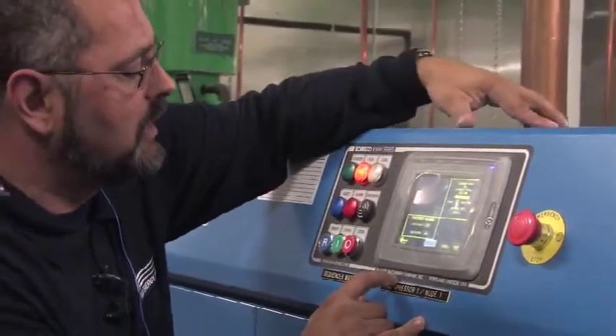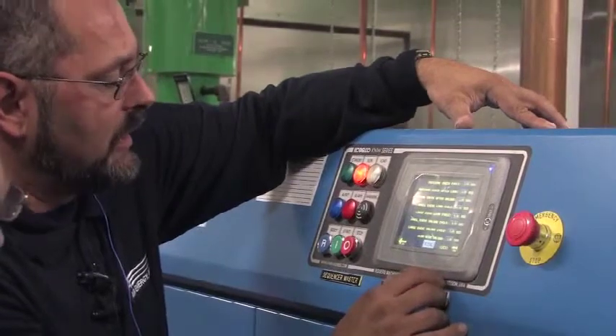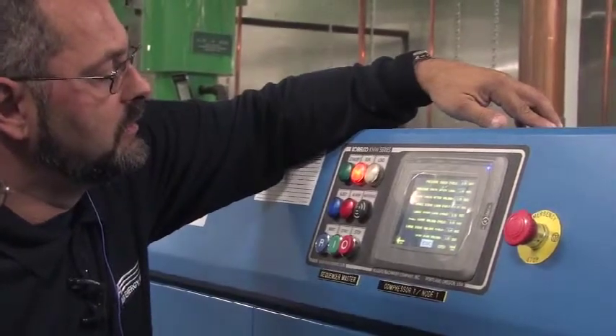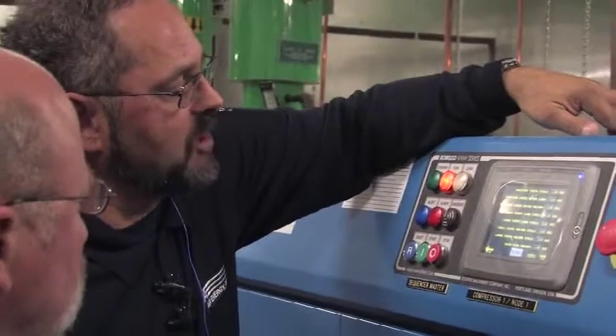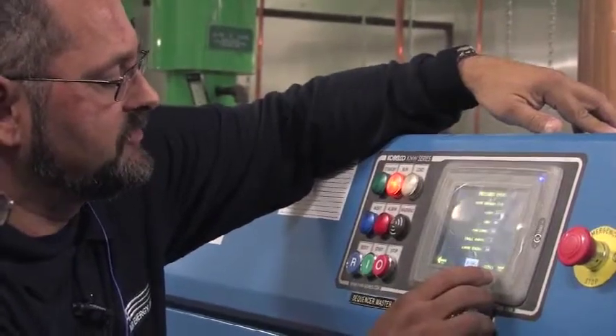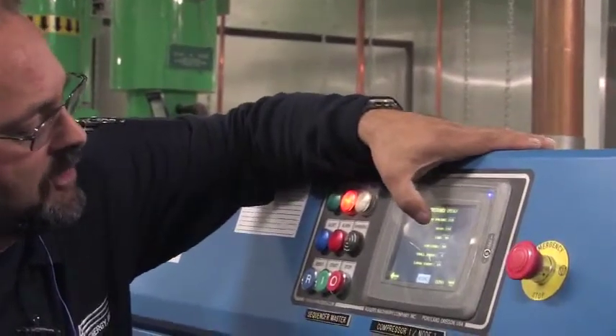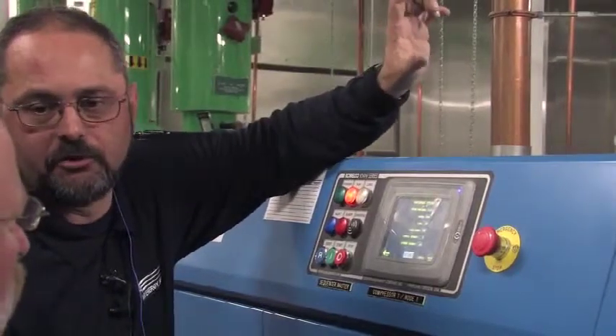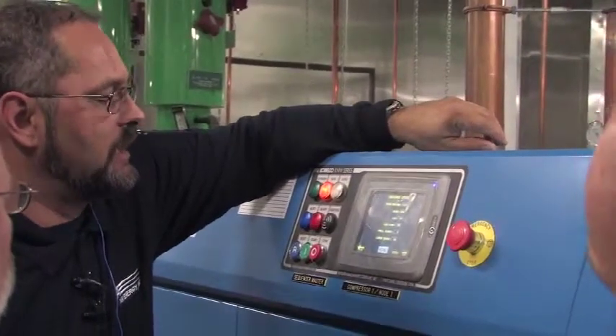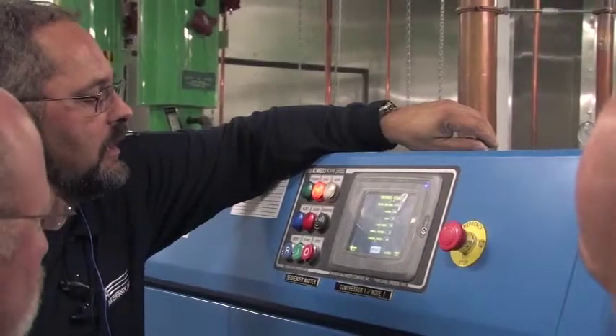Time clock, you know, if you got an alarm, pressure high and low. How often it checks the pressure: basically it scans every 2 seconds. Small event, large event cycles. These are all adjustments. Now this is what I was talking about as far as pressure. High and low is 110. The normal high and low are your settings where you want to keep the system. You know, that's what you're really looking to keep things between. So if it goes high or low, I'm going to get an alarm? Yes. And like I said, the events are from the factory, that was 2 and 3.